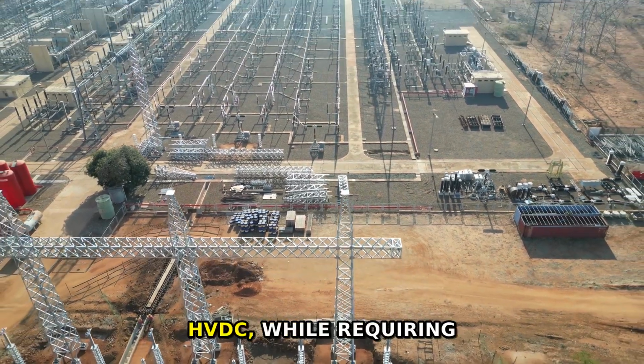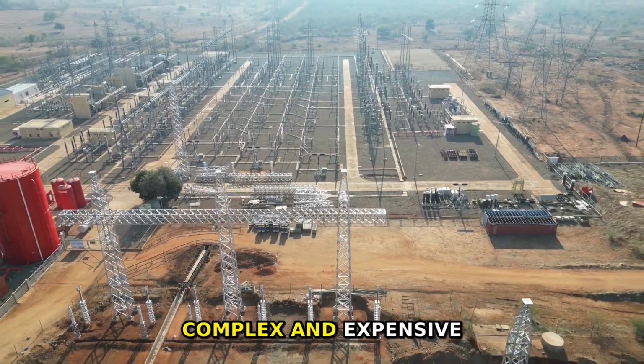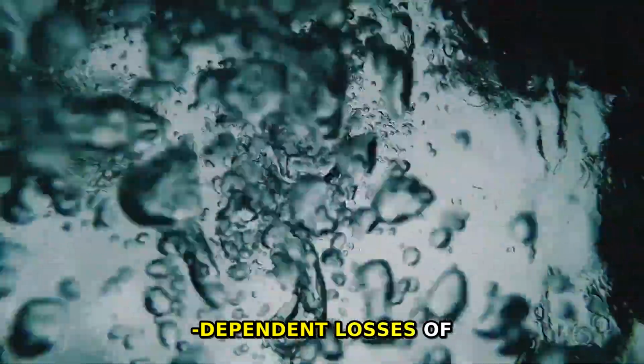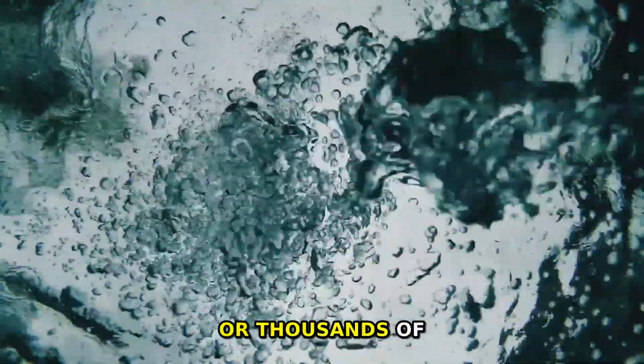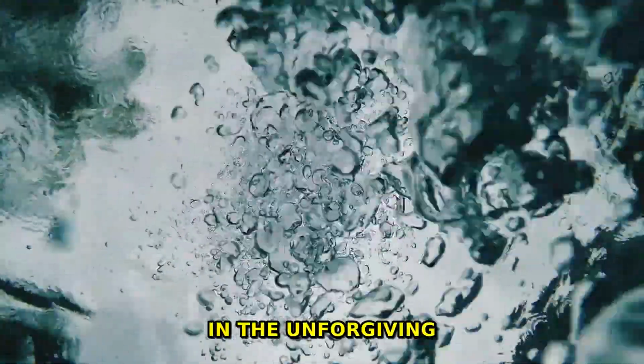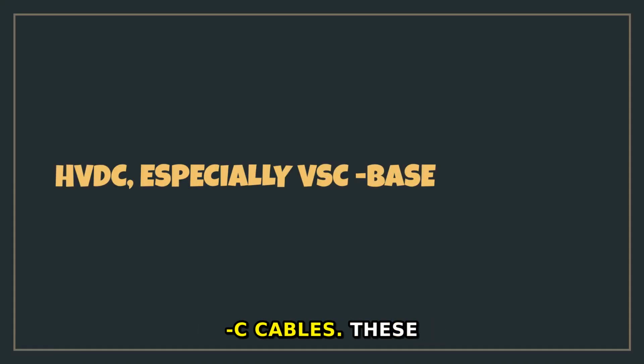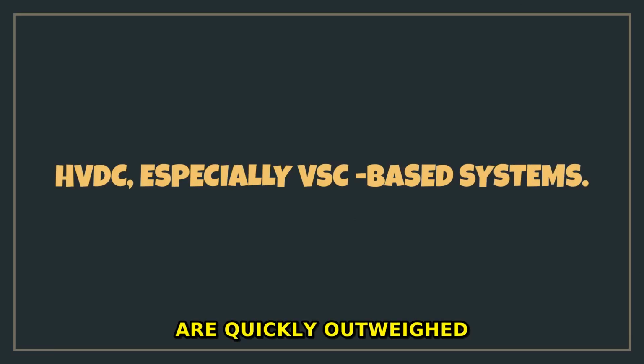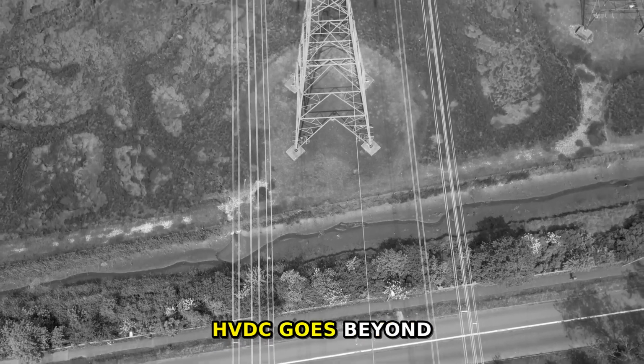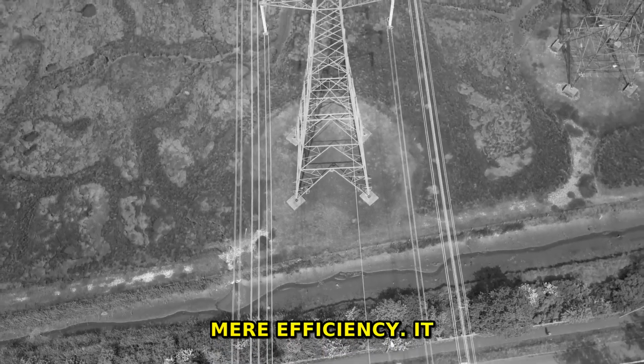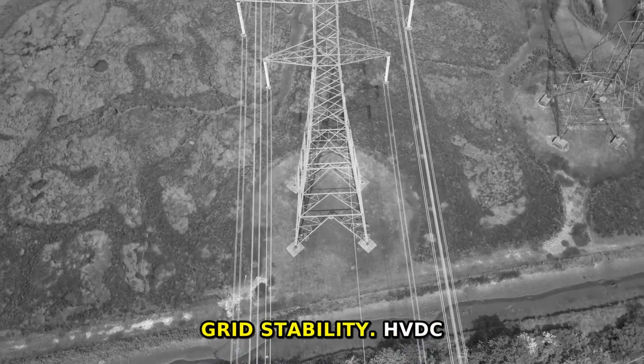The actual trick is that HVDC, while requiring complex and expensive converter stations at each end, eliminates the continuous, distance-dependent losses of reactive power and skin effect that plague AC transmission, especially over hundreds or thousands of kilometers, and critically, in the unforgiving environment of subsea cables. These initial upfront costs are quickly outweighed by the long-term energy savings and enhanced grid stability provided by HVDC, especially VSC-based systems. The unseen advantage of HVDC goes beyond mere efficiency. It also offers enhanced grid stability.